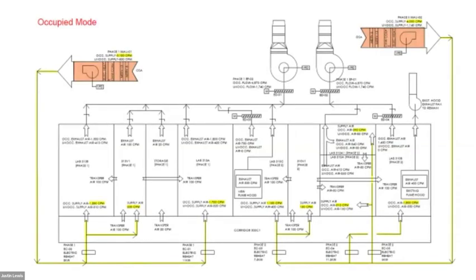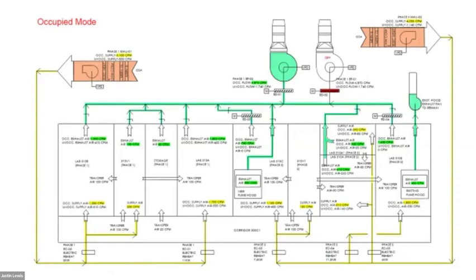We had both suites, two separate suites. Each suite had a dedicated makeup air unit, 100% outside air. There were no VAVs, there were no air valves. This was a hard set balancing damper balance, and each unit had a VFD. They also shared a common lab exhaust. Again, no VAVs, no air valves. This was just a hard balance.